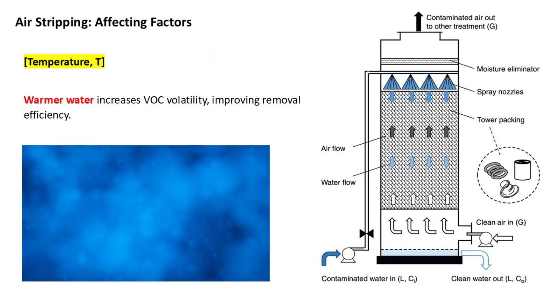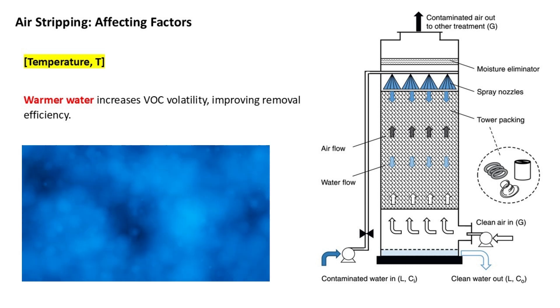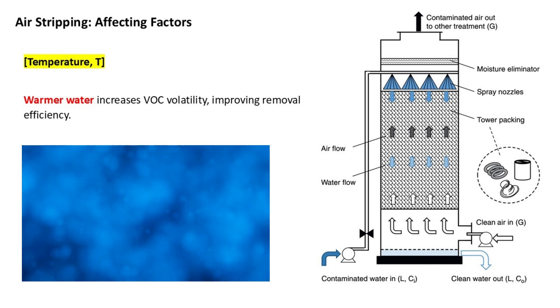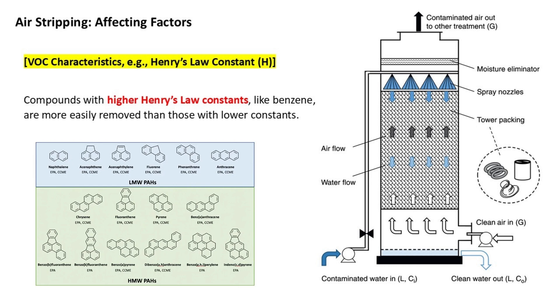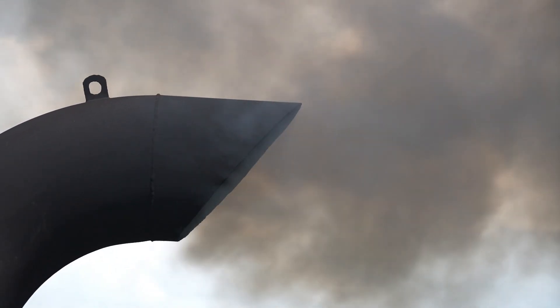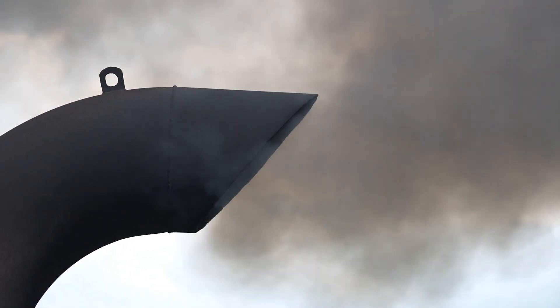Third, temperature: warmer water increases VOC volatility, improving removal efficiency. Fourth, specific VOC characteristics: compounds with higher Henry's Law constants, like benzene, are more easily removed than those with lower constants. While air stripping is effective for many VOCs, it has limitations. For example, it is not suitable for non-volatile or semi-volatile contaminants. Additionally, the treated air requires careful handling to prevent secondary air pollution.